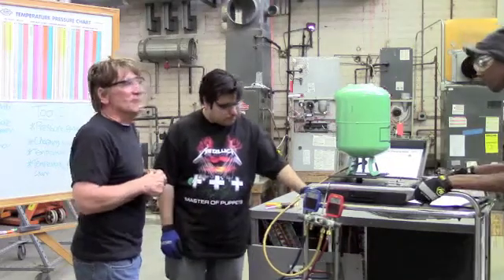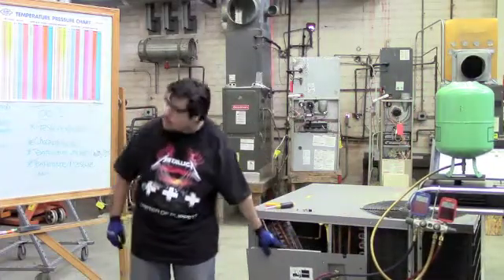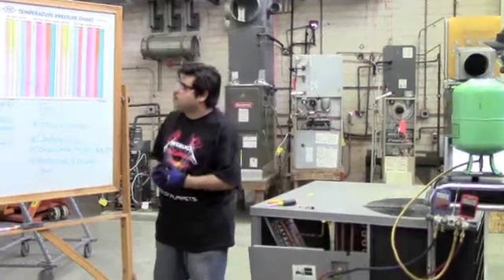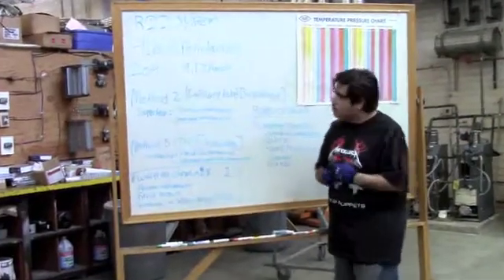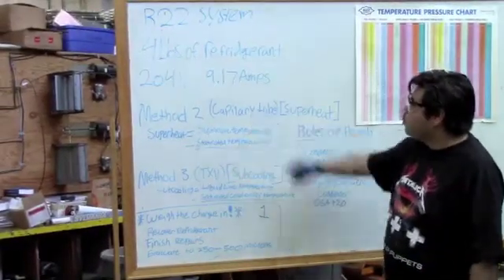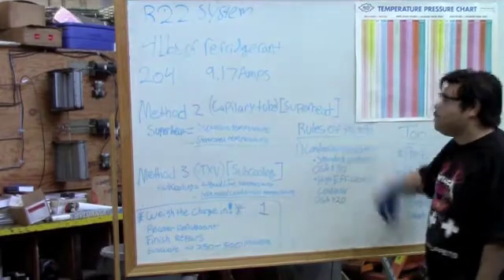I'm really interested in this, so let's take a look at my superheat. So our method number two, if you have any refrigerant left in the unit and you have no leaks or you have a capillary tube or orifice type of system, we're going to do superheat measurements.